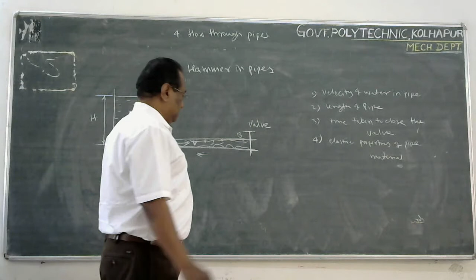So to avoid this water hammer effect, the first thing is you close the valve gradually. You have to close the valve gradually. And if you fit an air valve before this valve, the pressure waves or the increase in the pressure caused by stopping the momentum of the water will be absorbed here. Some water will go into the air valve, and these pressure waves may be absorbed.